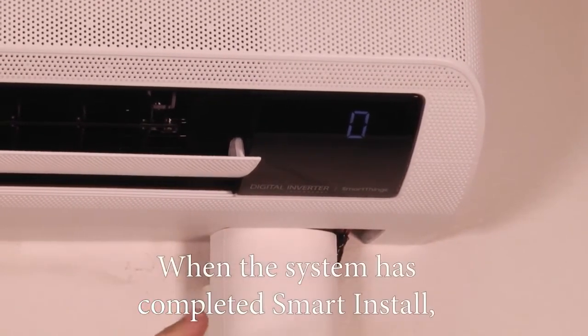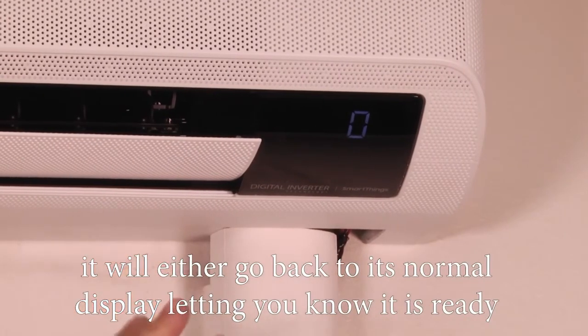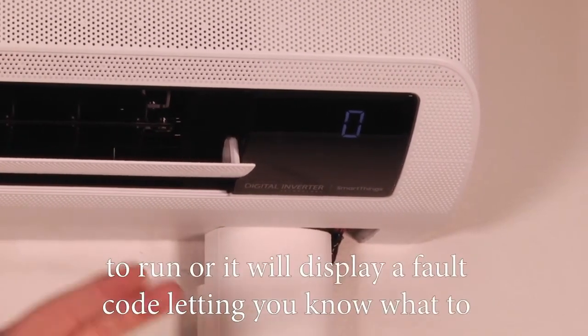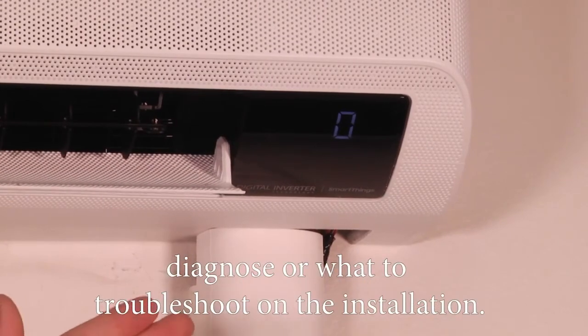When the system has completed Smart Install, it'll either go back to its normal display, letting you know it's ready to run, or it will display a fault code, letting you know what to diagnose or what to troubleshoot on the installation.